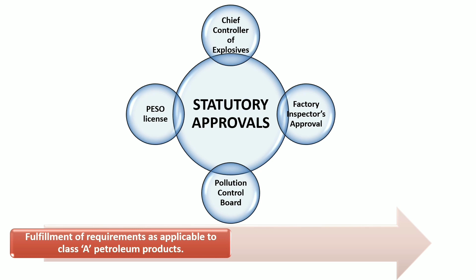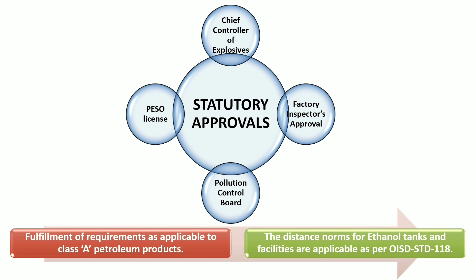Ethanol fulfills the criteria of a Class A petroleum product, hence all facilities, licenses and approvals required for the same are also applicable for ethanol. Inter-distance norms of OISD correspond to those of a Class A petroleum product. Ethanol is considered equivalent to a Class A petroleum product for having a flash point of 13 degrees Celsius. Also, in the National Electric Code, ethanol is put in gas group IIA alongside motor spirit and temperature class T2. All electrical fittings and fixtures shall be installed keeping this in mind.